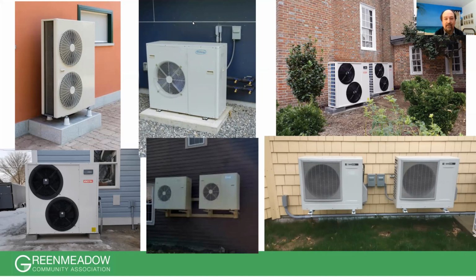The Chiltrix on high is only 49 dB, and the bigger unit coming out will be around 52 on high. It also has an advantage: you can program it to derate the unit a little, making the fan speed slightly slower, and in many cases without affecting performance. You can program the compressor too, to make everything quieter. I'm not aware of anybody else with the ability to tune the unit to the site like this, and it's mostly about the air from what I've seen.